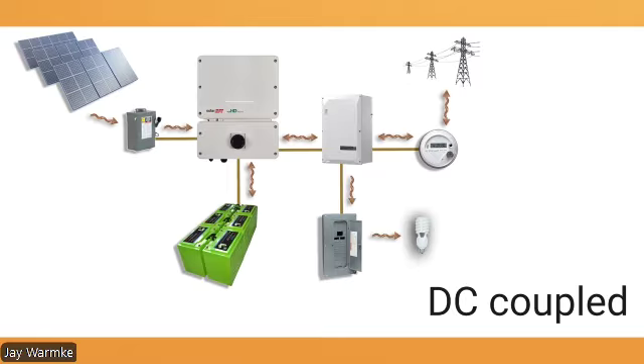If the grid goes down, it senses that and disconnects from the grid so that you're not backfeeding it, so that some worker out there isn't suddenly electrocuted because they think there's no power on the grid while you're pumping power onto it. This is known as islanding. So all inverters have an anti-islanding provision that keeps them from pumping back onto the grid.